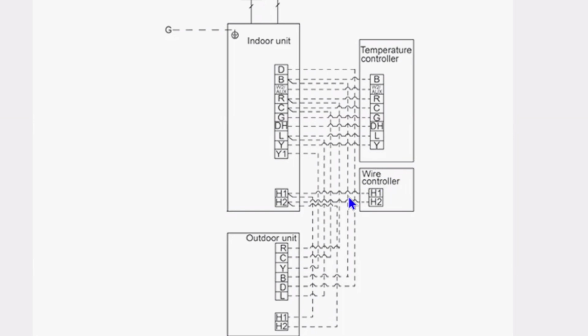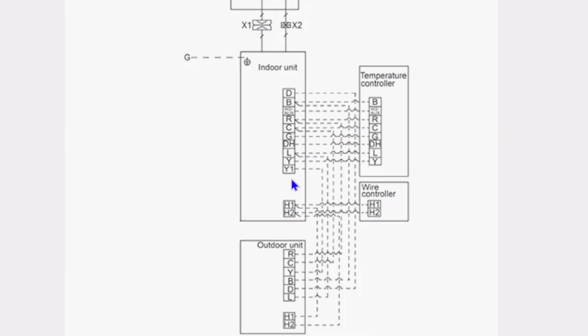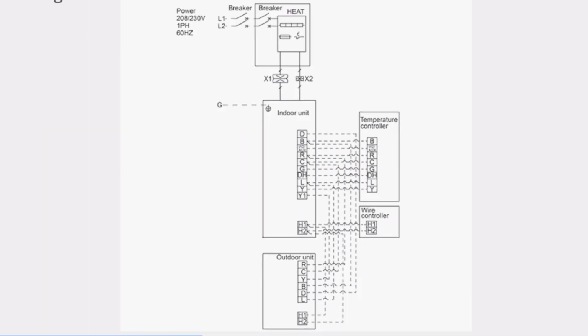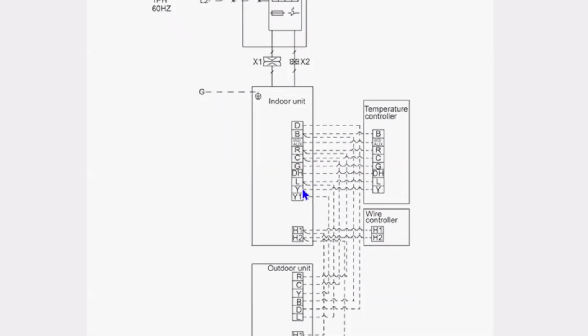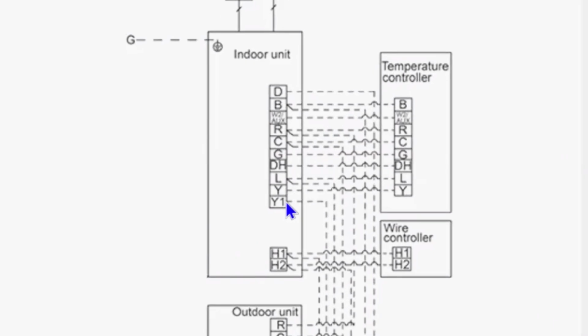But what I wanted to make sure you understood was H1 and H2 from the indoor to the outdoor, or even whether you got a controller or not, you do not have to have the H1 and H2 between the outdoor and indoor unit. We tested that here in the lab. We set it up for strictly 24-volt operation, and there was no issues with the unit functioning, which is the 24-volt thermostat. You will notice in the wiring, there is a Y that comes from the controller to Y on the indoor unit, and then from Y1, it goes out from there to the outdoor unit on Y.